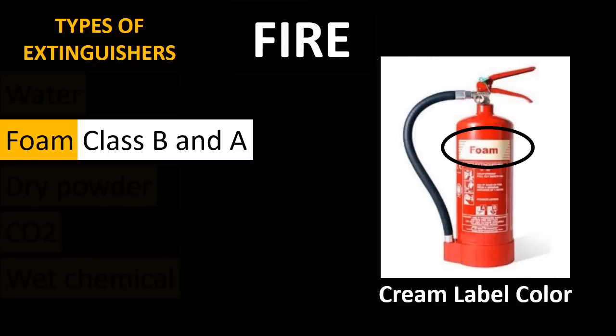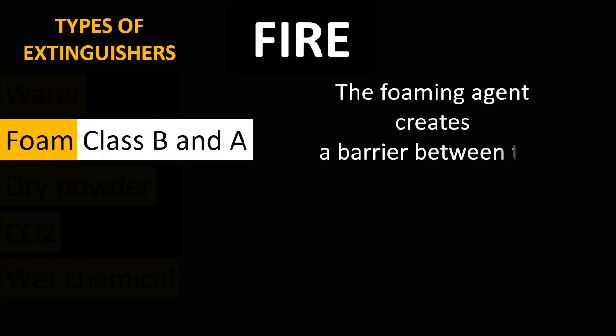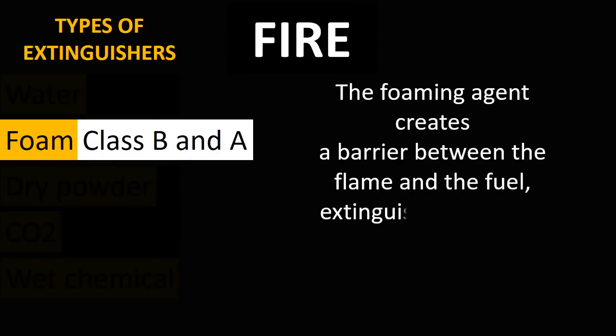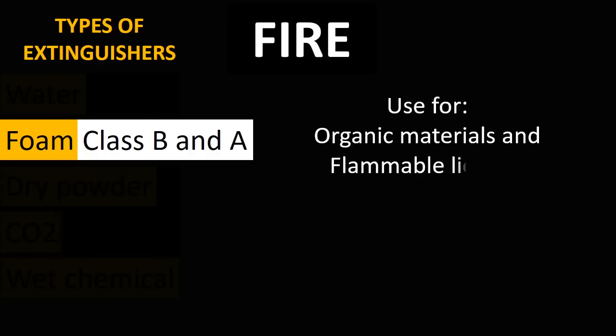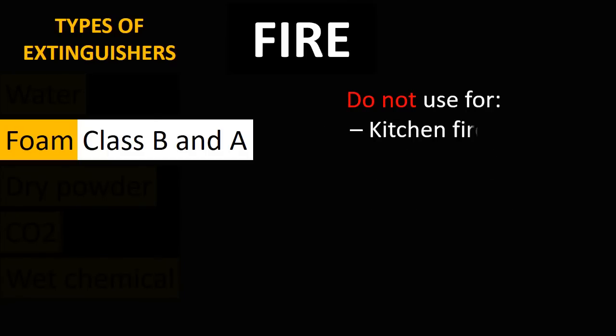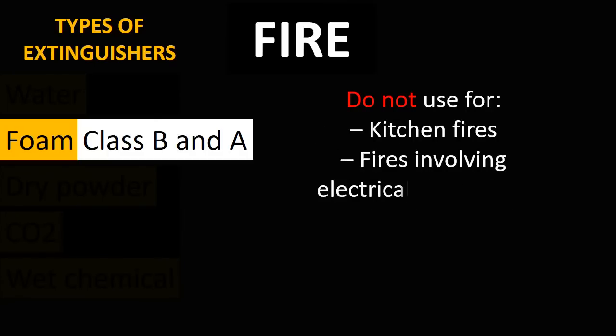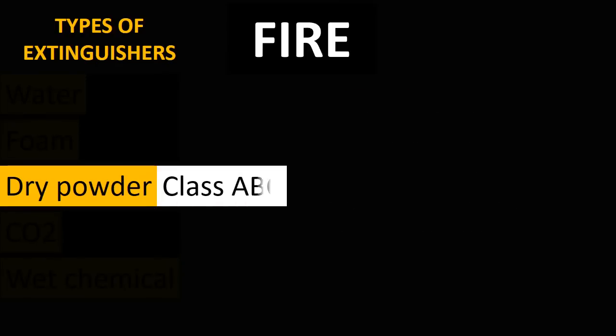The second type of fire extinguisher is foam type. Foam type is used on Class B and Class A fires and they have a cream label color. The foaming agent creates a barrier between the flame and the fuel, thus extinguishing the fire. This type is used for organic materials and flammable liquids like paint and petrol. Do not use foam type fire extinguishers for kitchen fires, fires involving electrical equipment, or on flammable metals.